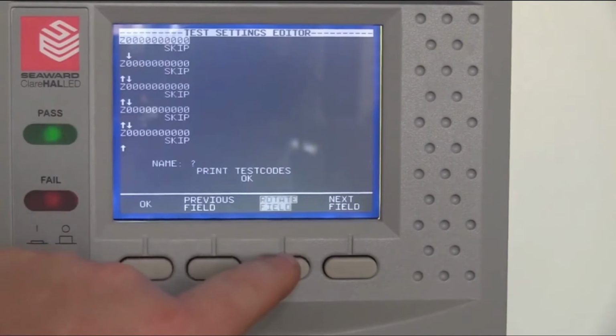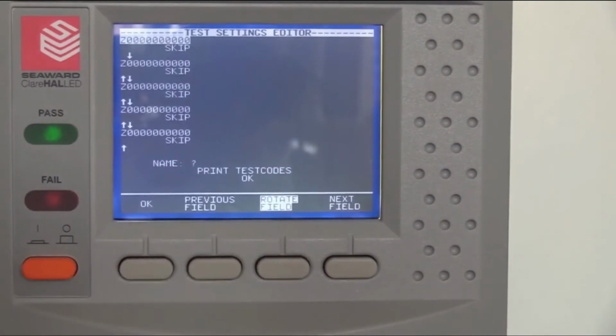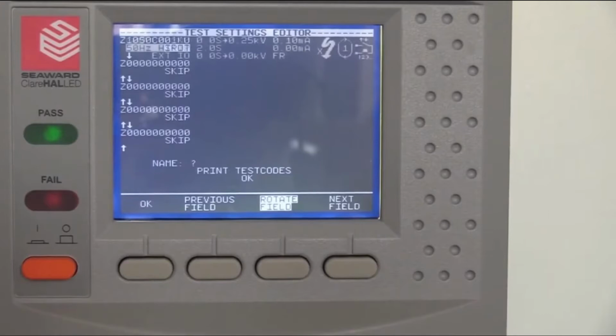I'm going to highlight the rotate field option. Now what that means is anytime I turn the wheel, that will alter the field which I'm trying to edit. And to move the cursor around, I simply use the previous and next field options. So let's move to our first test. At the moment it's skipped because there's no test programmed, and we simply use the wheel to define the test that we want to perform. So we're going to perform an Earthbond test. We can now set the parameters for the test up.